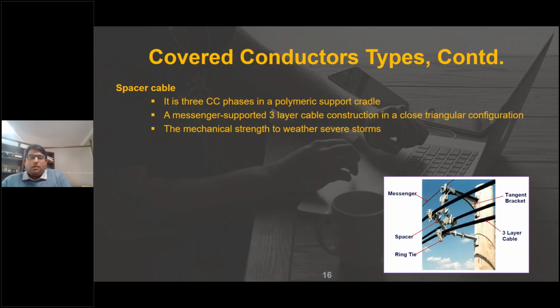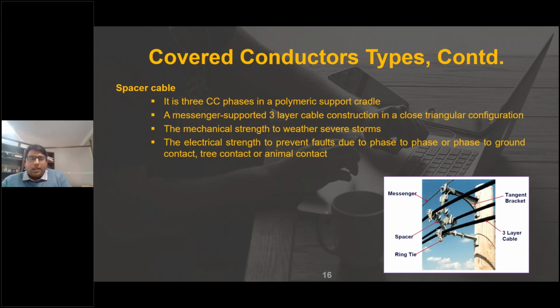It provides the mechanical strength to withstand weather or severe storms that may occur in the vicinity of those cables, and the electrical strength to prevent faults, such as phase to phase or phase to ground faults, because they are unsymmetrical faults, or animal contact. They provide electrical strength to prevent those faults basically, because this whole spacer arrangement with the pole and all those things provides very good mechanical strength to those conductors. They cannot be easily shaken.